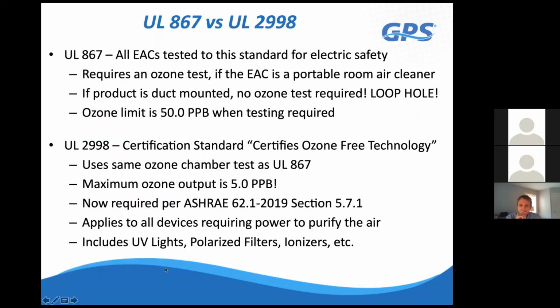And the reason ASHRAE felt it was necessary to force UL 2998 certification is that the UL 867 standard was not adequate as it pertains to electronic air cleaners. Electronic air cleaners are certified to UL 867, but all that standard really gives you is the ability to know that when you plug it into the wall, it's fused properly, everything's going to work, and it's not just going to catch on fire. So it's an electrical safety standard. But if the unit was a portable room unit, it would have to be tested for ozone.